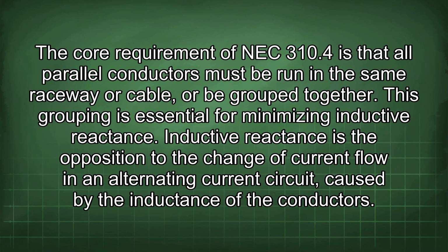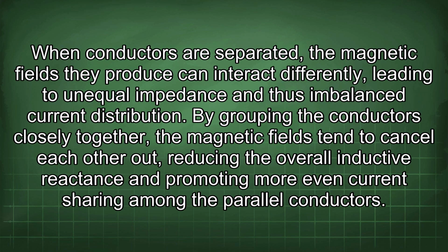The core requirement of NEC 310.4 is that all parallel conductors must be run in the same raceway or cable, or be grouped together. This grouping is essential for minimizing inductive reactance. Inductive reactance is the opposition to the change of current flow in an alternating current circuit caused by the inductance of the conductors.